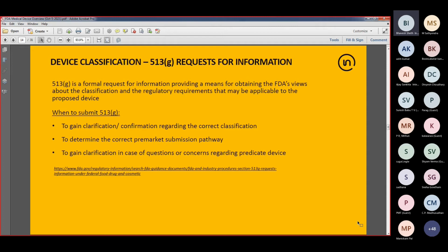You don't always need to submit this inquiry. If you know your classification from the device classification database, or knowing a product that a competitor is selling and that your product is very similar, that's often enough to confirm the classification. But when you are dealing with a device for which you can find no information on the FDA device classification database, and you want to get clarification or confirmation regarding your approach and the correct classification, then it's good to submit a 513G. If you are unsure about the regulatory submission type, again, you can submit a 513G request to FDA.